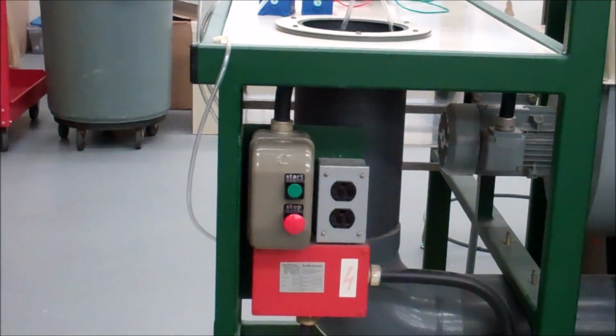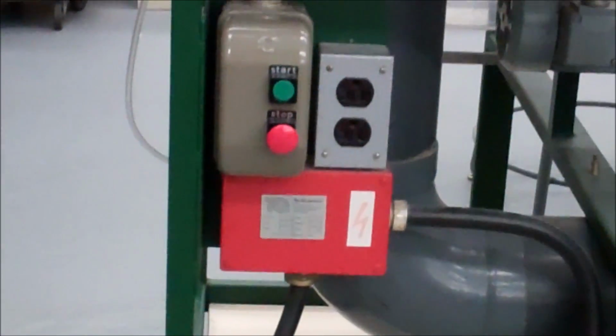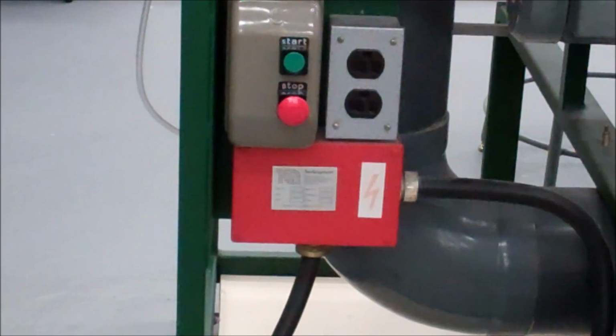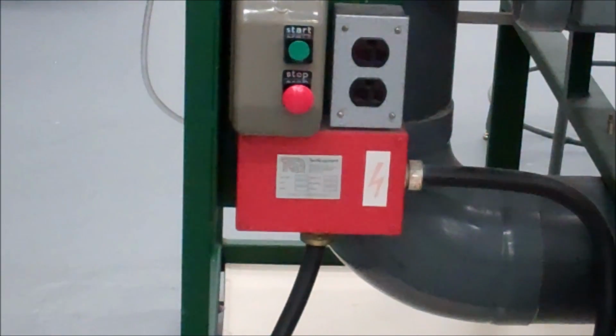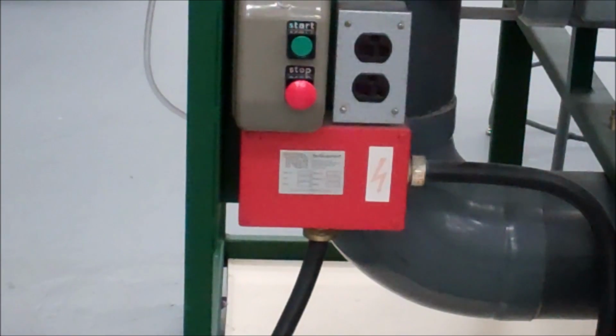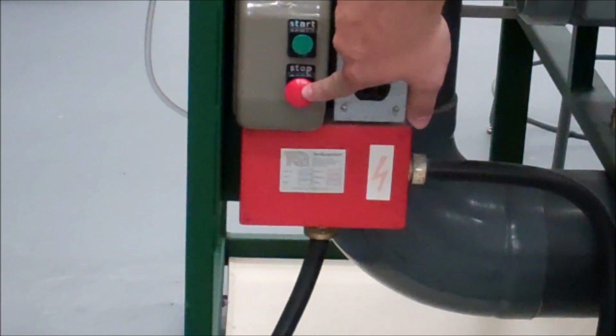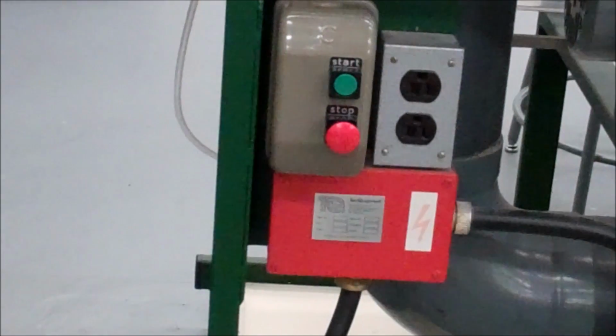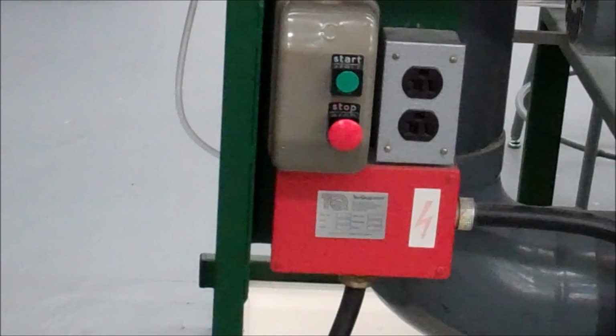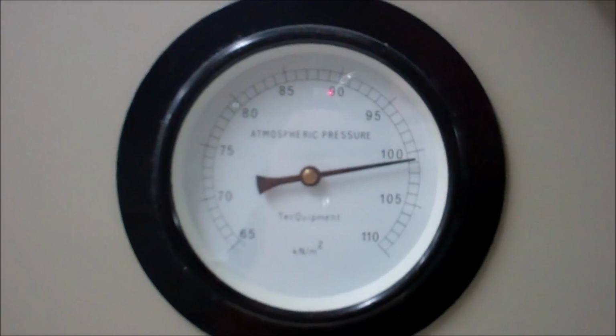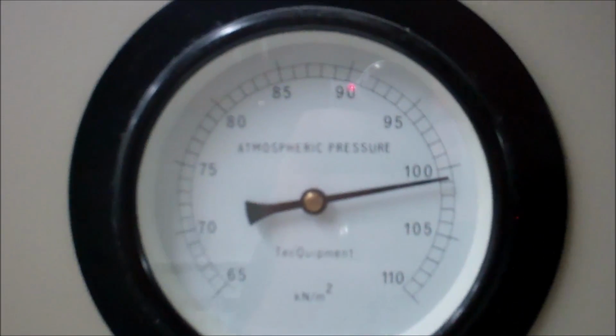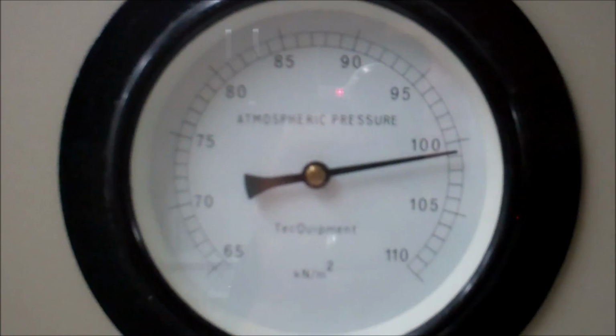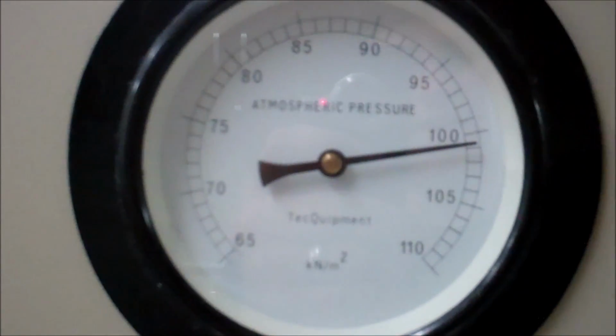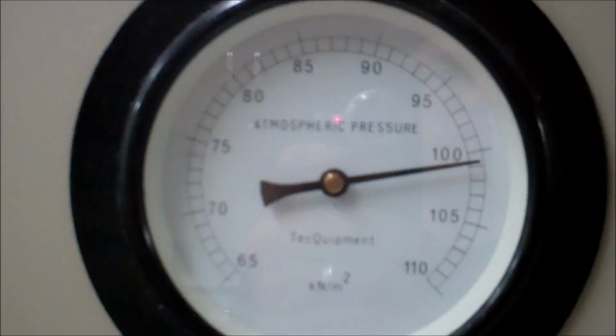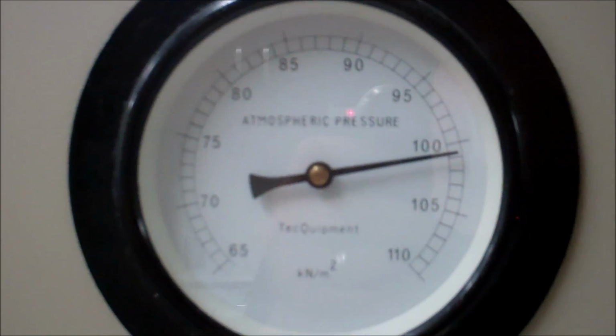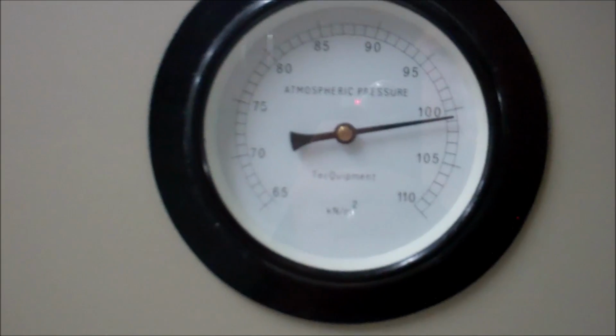There's a control panel on the side here. You can see a green and a red button. To start it, you press start, and then it starts the flow bench. To stop it, you press the stop button. Now before you take any measurements, you always want to have the flow bench running for a few seconds, then take your measurements. The dial on the actual flow bench, and you see here it says atmospheric pressure on the dial, and you can read what the pressure is in ambient. Now keep in mind that this is in kilonewtons per meter squared, so this is in kilopascals, so you need to convert that to pascals before you calculate your static pressure.